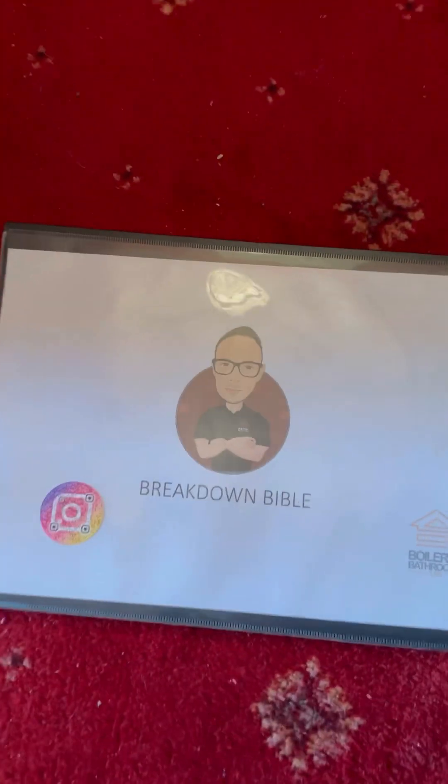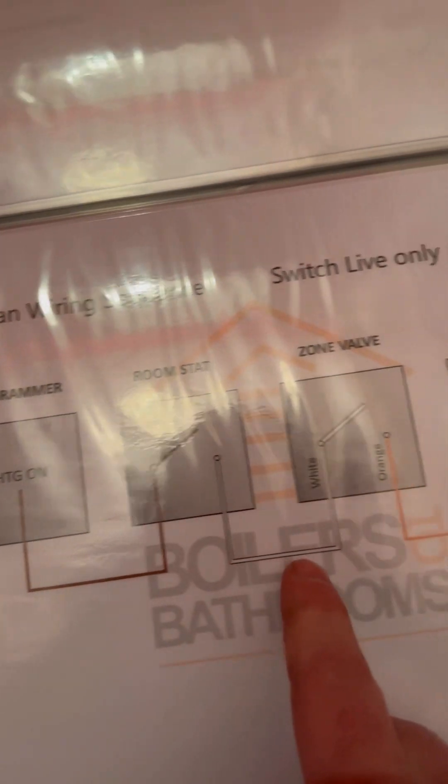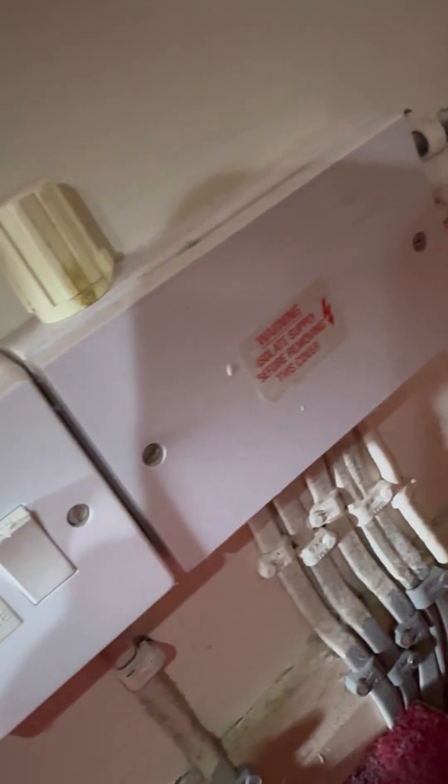Whip out the breakdown bible, but this time we're going to do it a little bit differently rather than follow the flow chart. There's the wiring diagram for heating on. We know that it goes from the programmer to the room stat which downstairs is right next to each other, and then up to the zone valve on white.